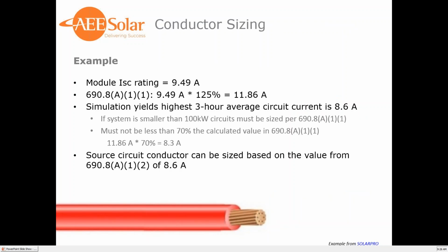So here's a quick example. If you have a module, ISC rating is 9.49. The standard calculation method in 690.8A11 would be 9.49 times 1.25. Actually, I didn't include continuous duty rating in here, so that's why I'm only using one of the 1.25 multipliers. So that would have to be added in after. The simulation yields 3-hour average circuit current is 8.6 amps. If the system is smaller than 100 kW, the circuit must use the standard method. And also it must not be less than 70%. So 70% of our calculated method, or calculated from the A11, would be 8.3 amps.